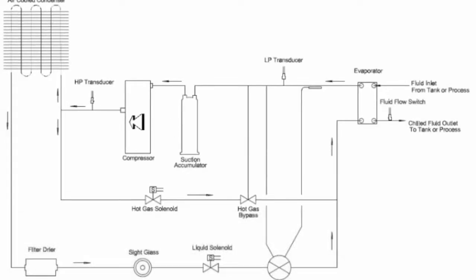So let's take a look at the hot gas bypass system in a process chiller. We'll start here at the compressor, and on the outlet of the compressor you have a discharge line. There are two courses of travel for your hot gas. One is to your condenser and one is down here towards your hot gas system. Now there are two important components to the hot gas system. One is the hot gas solenoid and the other is your regulator valve.